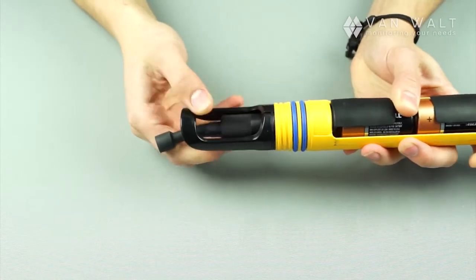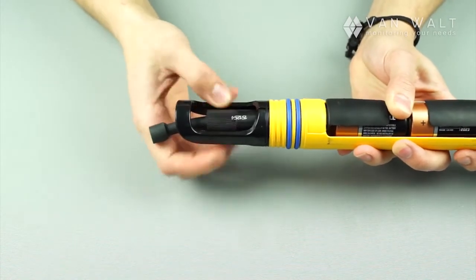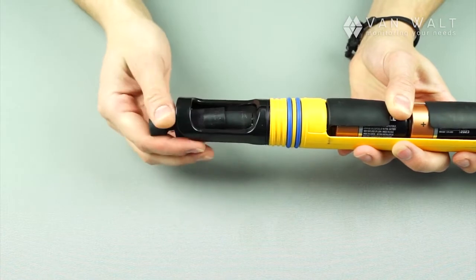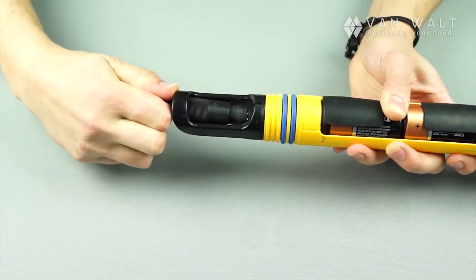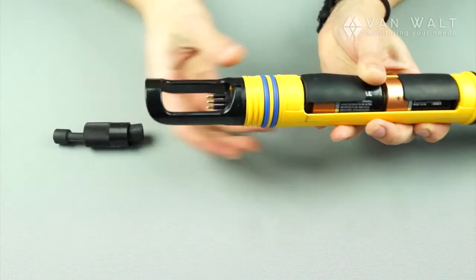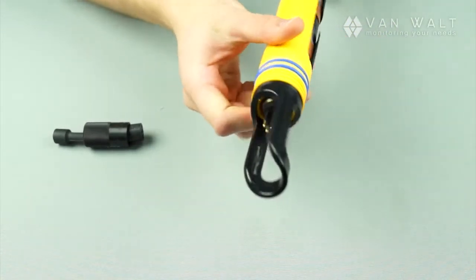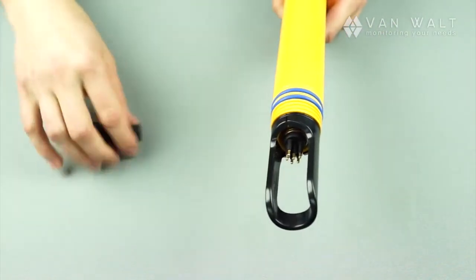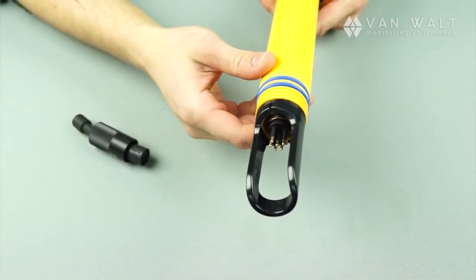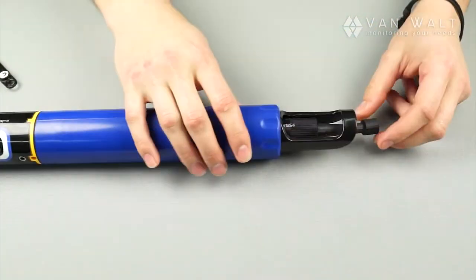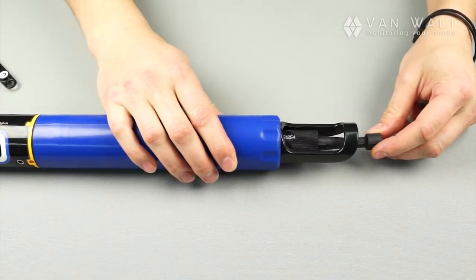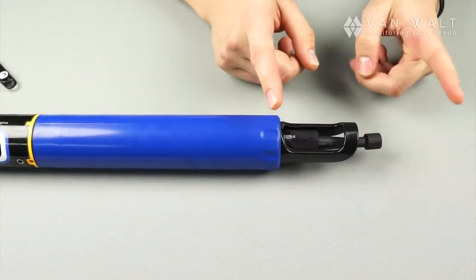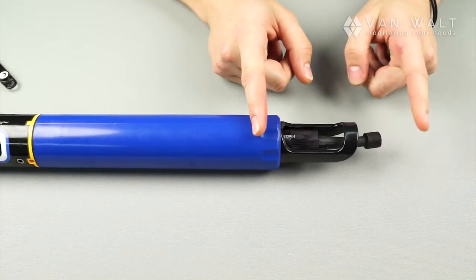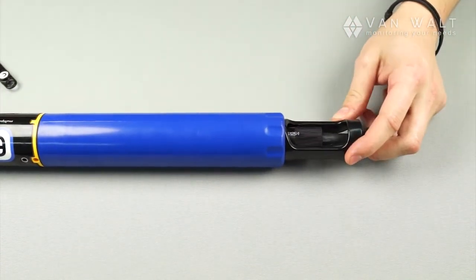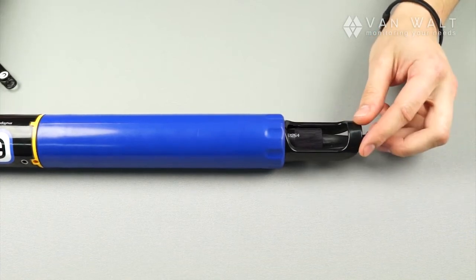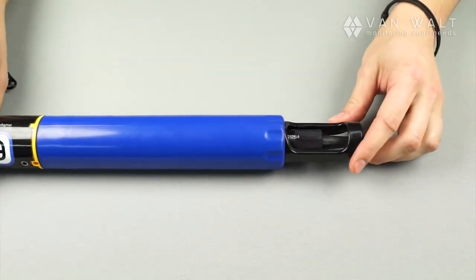Underneath here is a screw connector. This is where we would attach our vented cable for our telemetry, or USB if PC logging is required. Again, all of the connectors here are wet mateable connectors, just like our probes have. In addition to being able to connect the device to your computer via a USB adapter on this end here, 99% of your connection can actually be done via Bluetooth, so you don't need your computer in your calibration area at all to do your calibration.